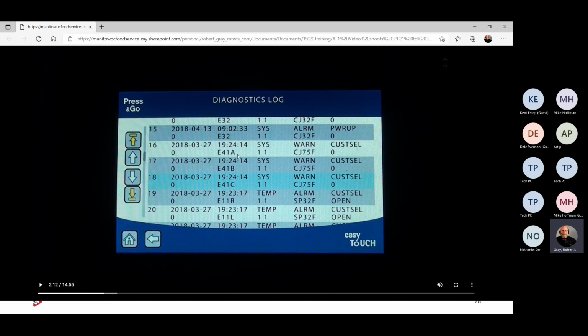Now, if you have a single A, for example, 41A, you're simply going to check the incoming voltage to that load contactor for the lane, from A to B. And I'll show you this in a diagram. At that point, it's going to be the black to the red wires. If I have it going into the input of the contactor, I'm going to check the output. If I don't have it, at that point I'm going to say, wait, why do I not have it? Check the other phases as well, which they should be fine.